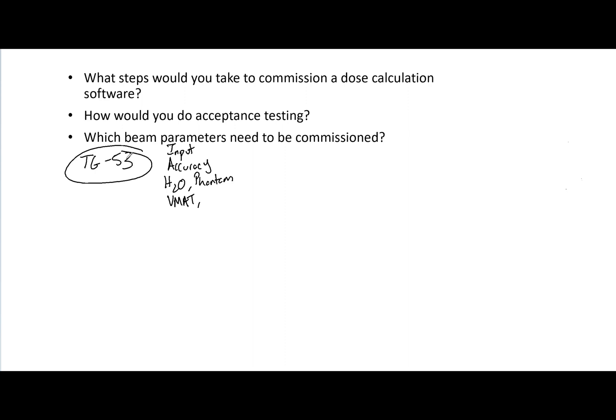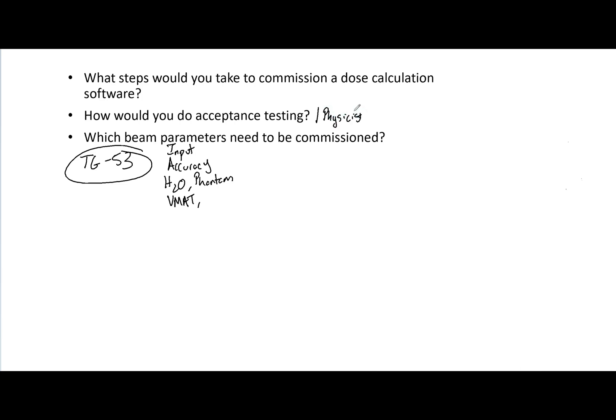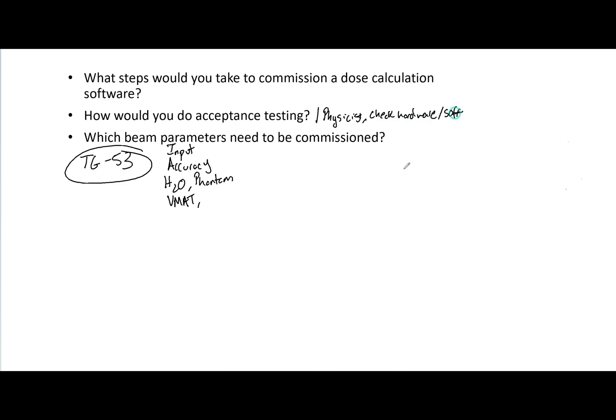Now, for acceptance testing, again reference TG53. Normally this involves only one physicist — remember the difference between commissioning and acceptance testing. For acceptance testing, you want to check the hardware, check the software, and then verify the accuracy of the dose calculation in specific circumstances.